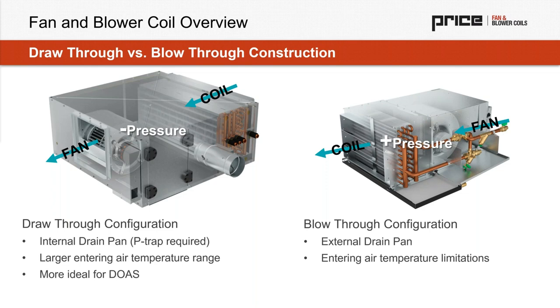Now, why does this matter? Why would a mechanical consultant care? Well, the change in configuration of those components influences the construction of the equipment. Generally, blower coils are heavier gauge, heavier duty, more sealed, while fan coils can have some lighter gauge material by the nature of their construction. And the real reason for that is the pressurization of the casing.